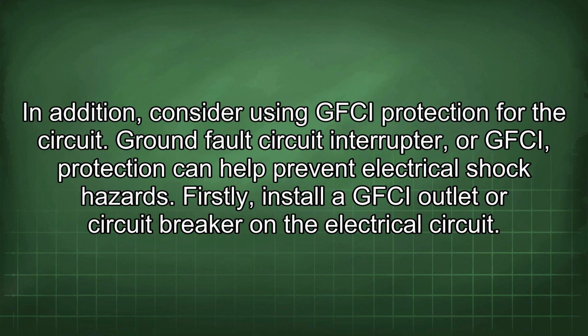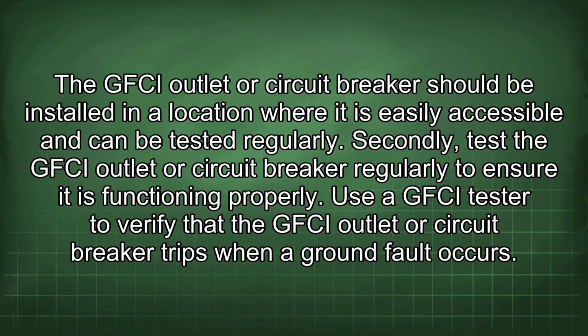Ground fault circuit interrupter, or GFCI, protection can help prevent electrical shock hazards. Firstly, install a GFCI outlet or circuit breaker on the electrical circuit. The GFCI outlet or circuit breaker should be installed in a location where it is easily accessible and can be tested regularly. Secondly, test the GFCI outlet or circuit breaker regularly to ensure it is functioning properly. Use a GFCI tester to verify that the GFCI outlet or circuit breaker trips when a ground fault occurs.